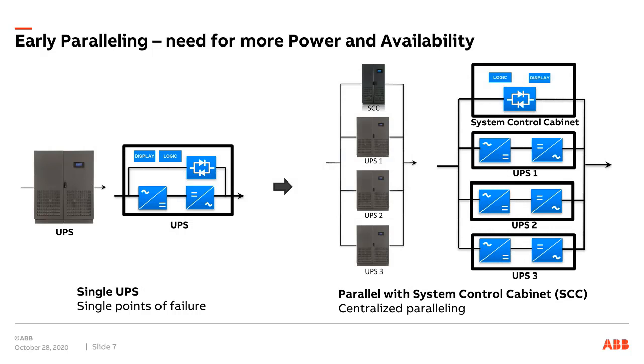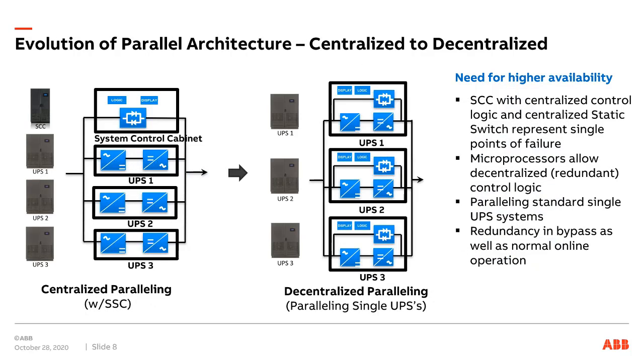And so that was the beginning of paralleling. And then the next step in the development ties back to, and I guess part of the reason for talking about this is also illustrating that sometimes history repeats itself, or you could also say we learn from history. And I'll get down to that later in the presentation. But I guess the industry learned the same lesson again. We have the traditional paralleling with a centralized paralleling control with a system control cabinet on the left. And again, anything man-made will fail at some point. If what fails with this configuration is an inverter, it's not so bad if we have N+1, like we have 1 extra. But if anything fails in the system control cabinet, it's still a bad day.